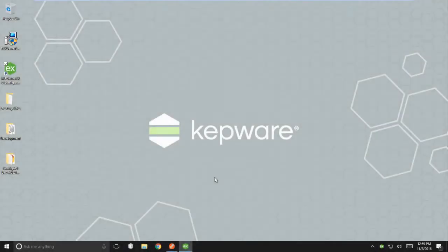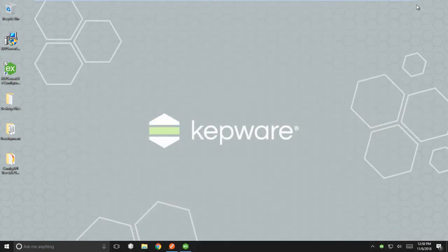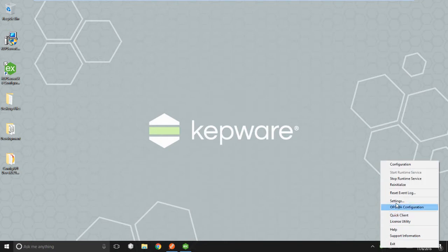Now let's move on to a demo of this feature. Note that this demo will use SimDemo.opf project that is loaded in all fresh installs of KepServer EX. To enable the API, right click on the administration icon for KepServer EX in the task tray on the local machine where the software is installed. Select settings and open the configuration API service tab.